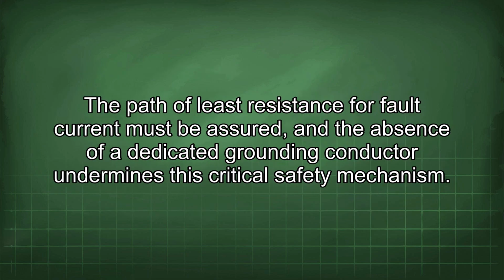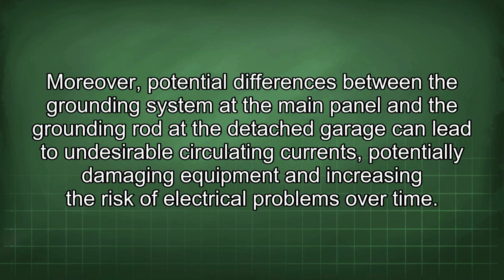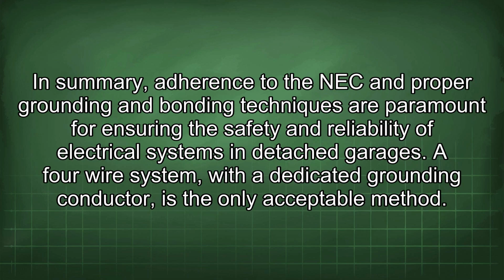The path of least resistance for fault current must be assured, and the absence of a dedicated grounding conductor undermines this critical safety mechanism. Moreover, potential differences between the grounding system at the main panel and the grounding rod at the detached garage can lead to undesirable circulating currents, potentially damaging equipment and increasing the risk of electrical problems over time. In summary, adherence to the NEC and proper grounding and bonding techniques are paramount for ensuring the safety and reliability of electrical systems in detached garages. A 4-wire system with a dedicated grounding conductor is the only acceptable method.